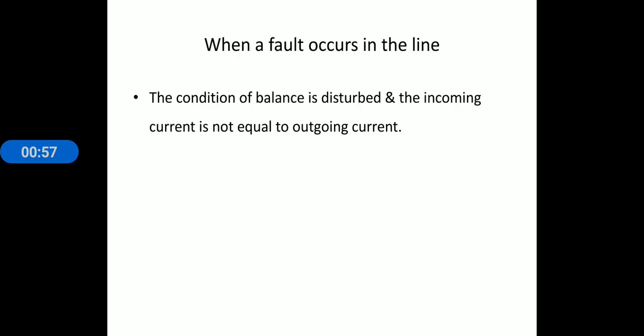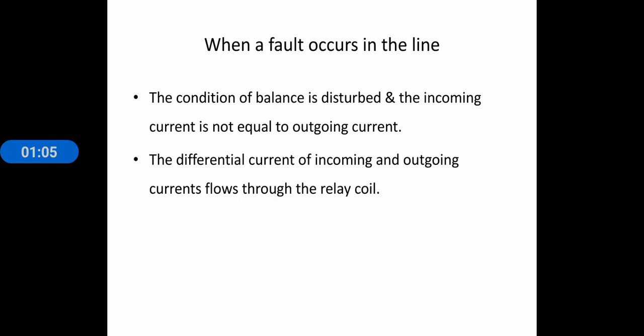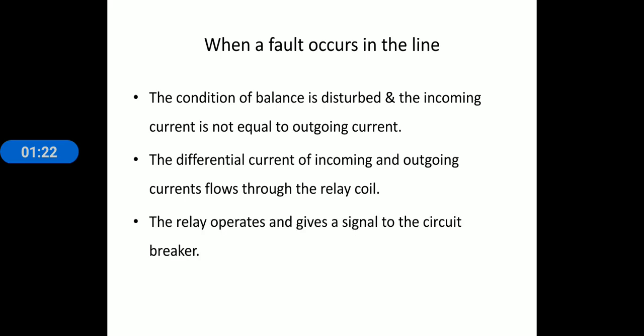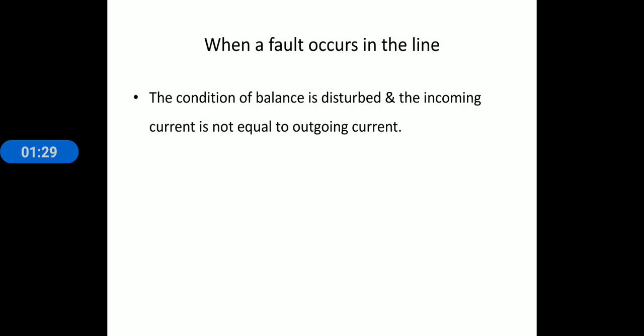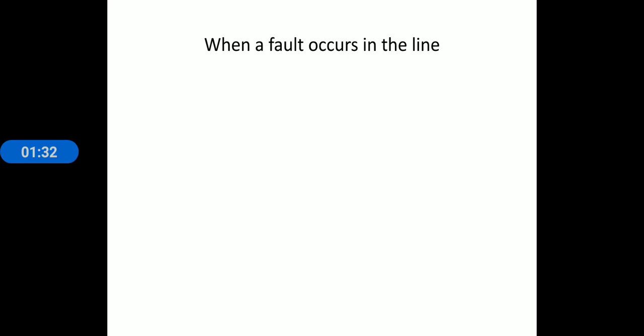When a fault occurs, it disturbs the balance, and the incoming current is not equal to the outgoing current. At that time, the differential current of the incoming and outgoing currents flows through the relay, and the relay sends a signal to the circuit breaker, and the circuit breaker trips the circuit and isolates the faulty section. That is the general explanation for differential pilot protection.